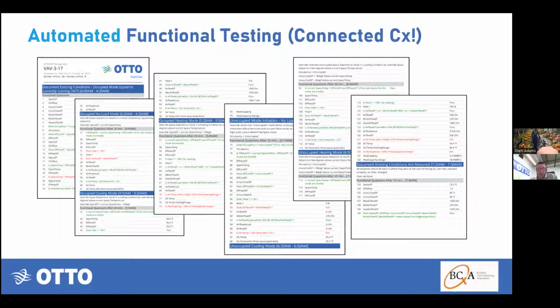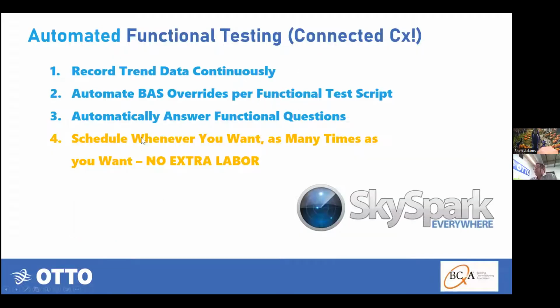What connected commissioning enables us to do is automate much of that acceptance phase scope. We're talking about recording trend data continuously, independent of the contractor, so they don't need to set up trends. I know they have their scope, usually it requires them to set up trends, but it's most common that that's one of the last things they do for you. I heard a commissioning provider at the conference point out that probably only 1 out of every 20 projects does he get trend data ahead of functional testing. And this is trend data that's often required in the contract. It just doesn't happen. It's a shame, but that's what connected commissioning makes a whole lot easier.